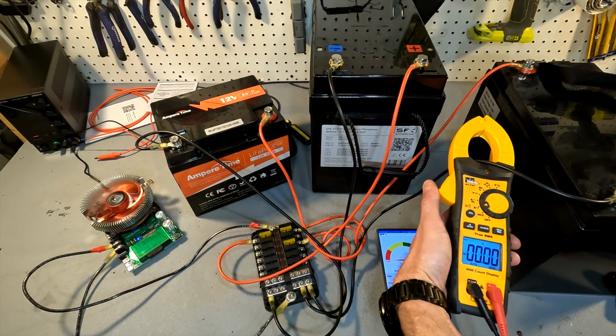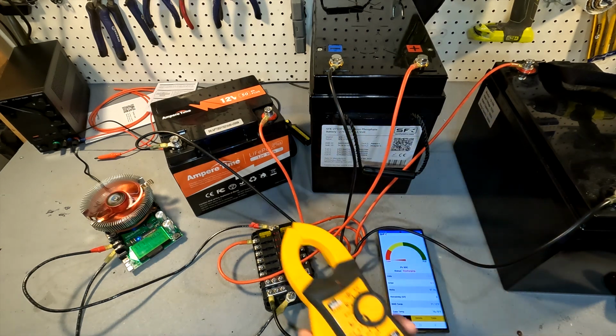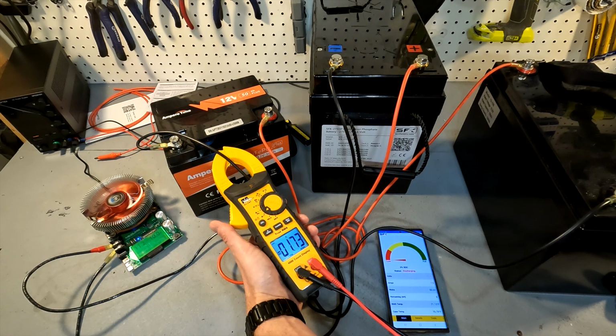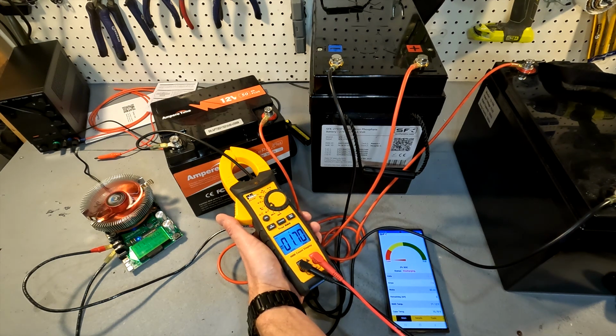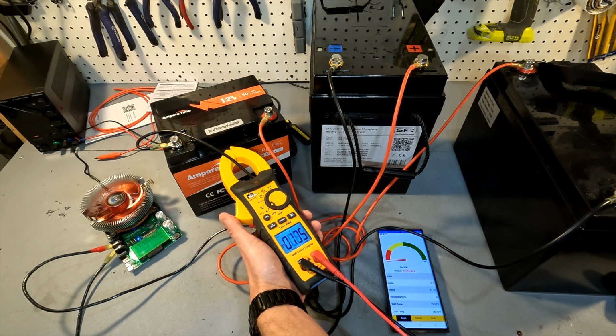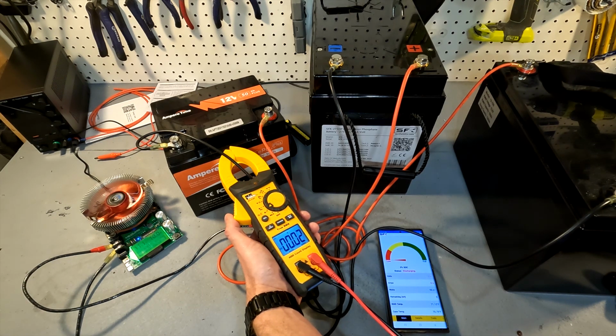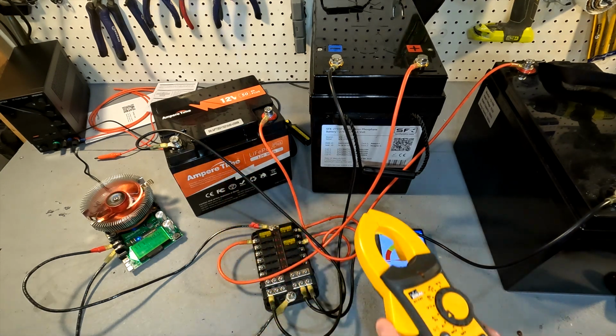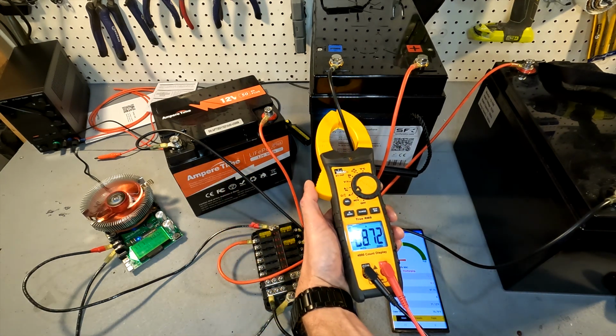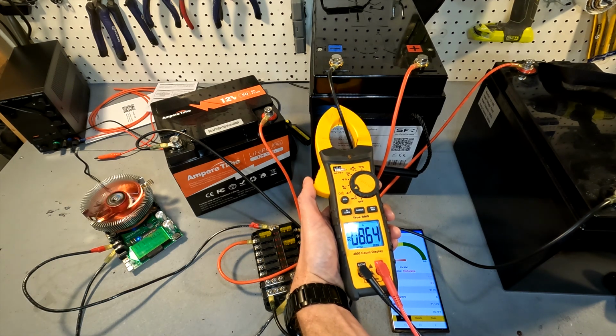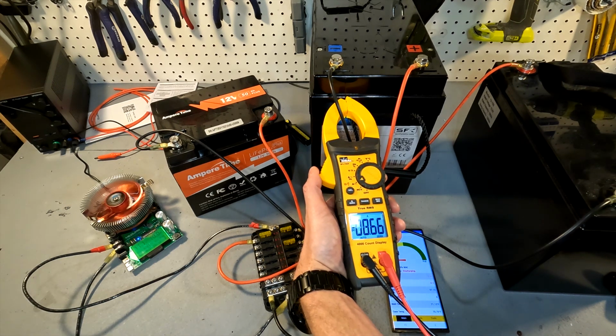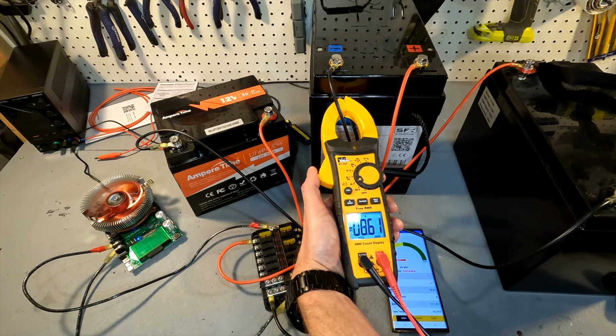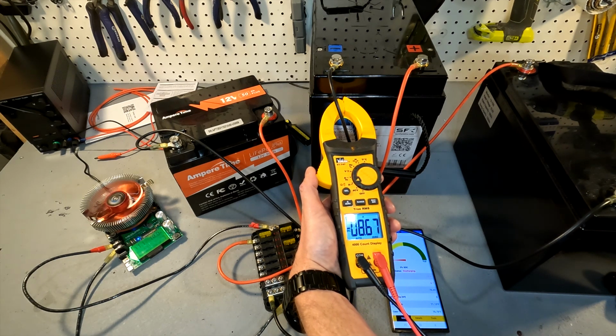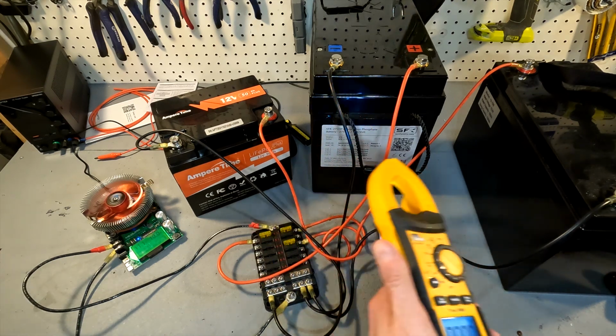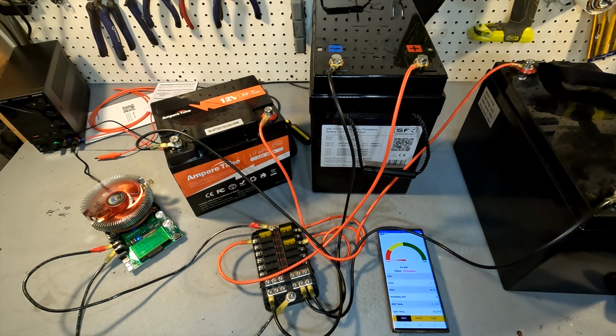So this battery and the Ampere time battery are both struggling. They're waking up, then the BMS shuts off again, and they wake up and shut off again. Meanwhile this battery is still constantly pulling, compensating between the two. It's pulling 8.6, then 6.7, then right back up to 8.6. So these batteries are all on the verge of dying.